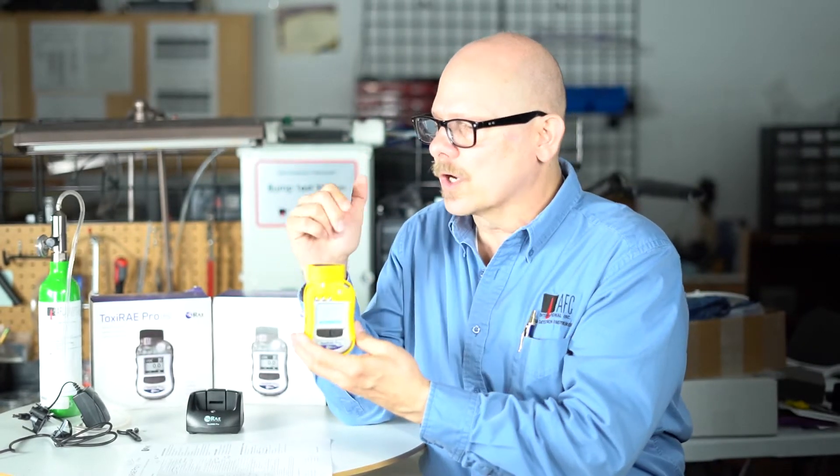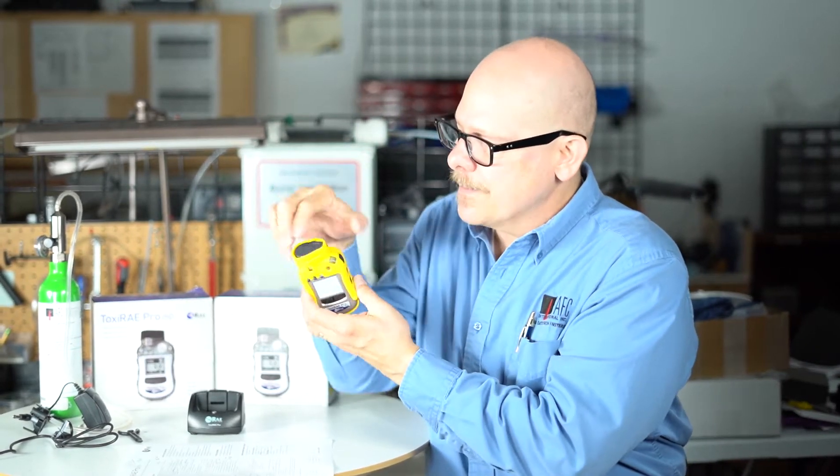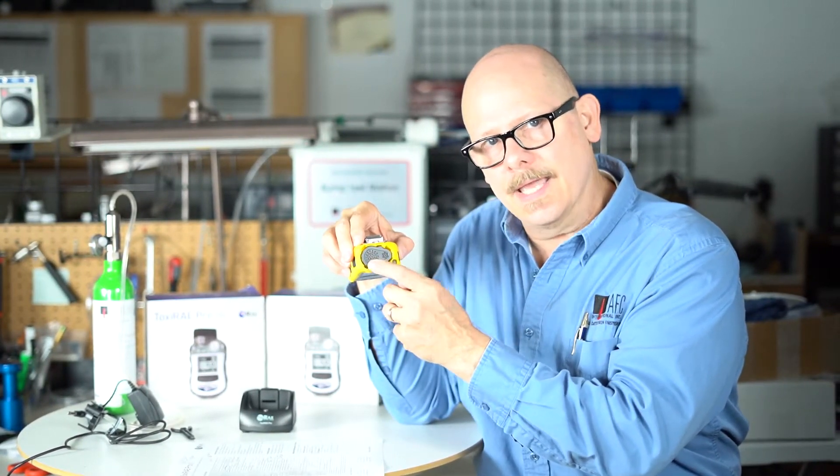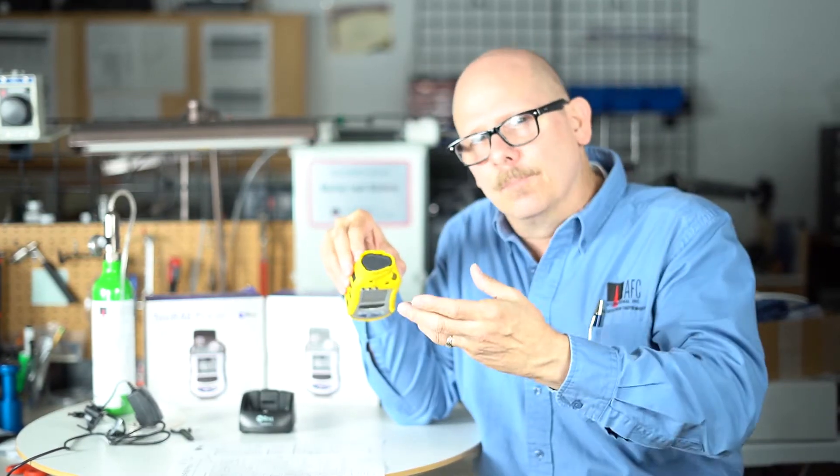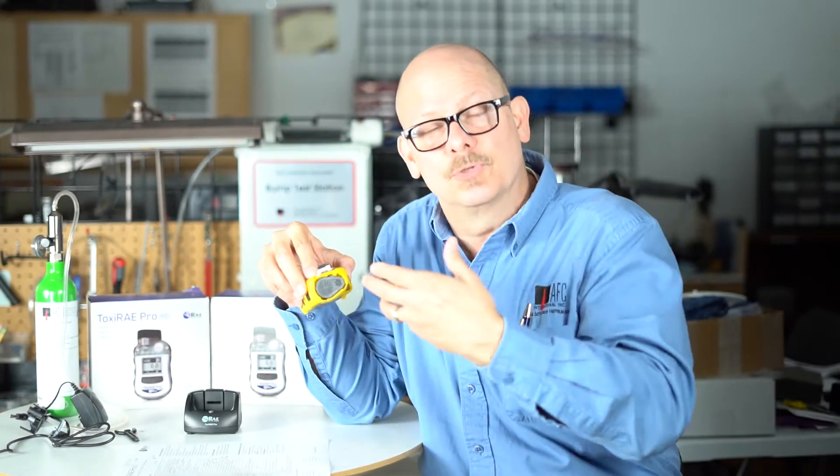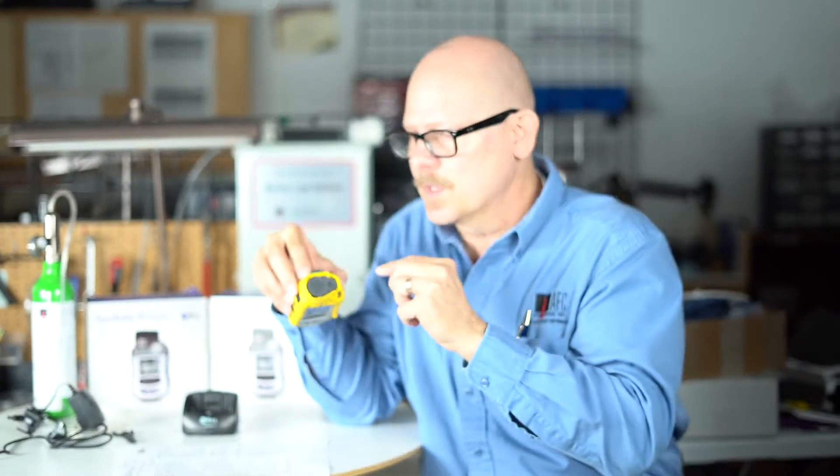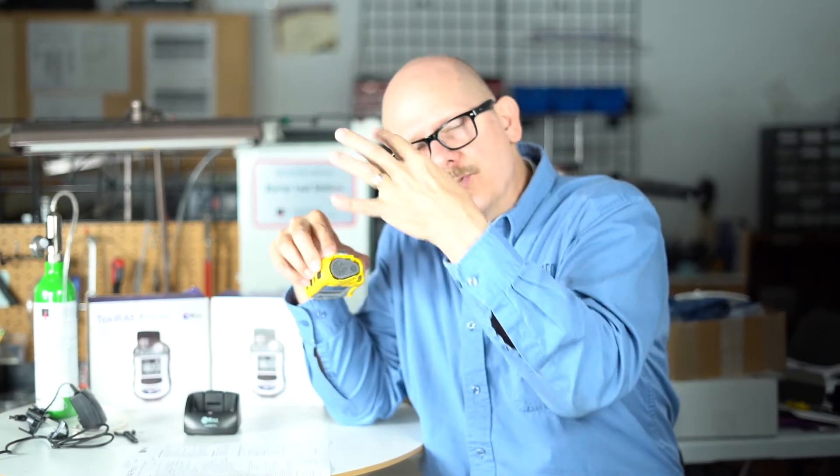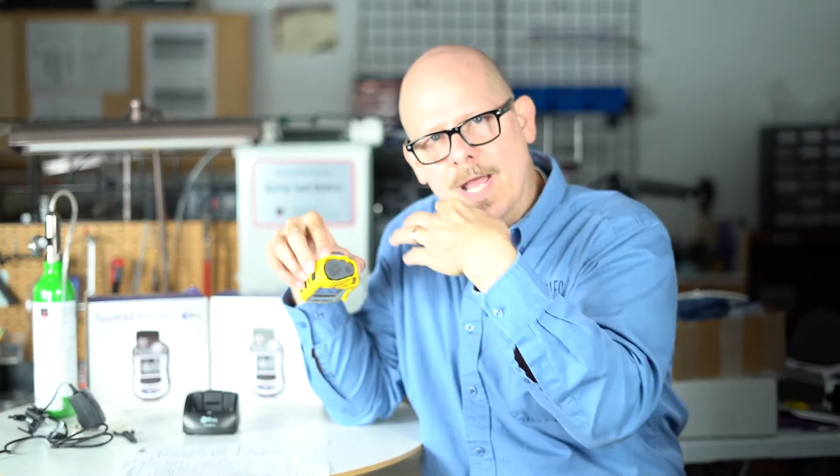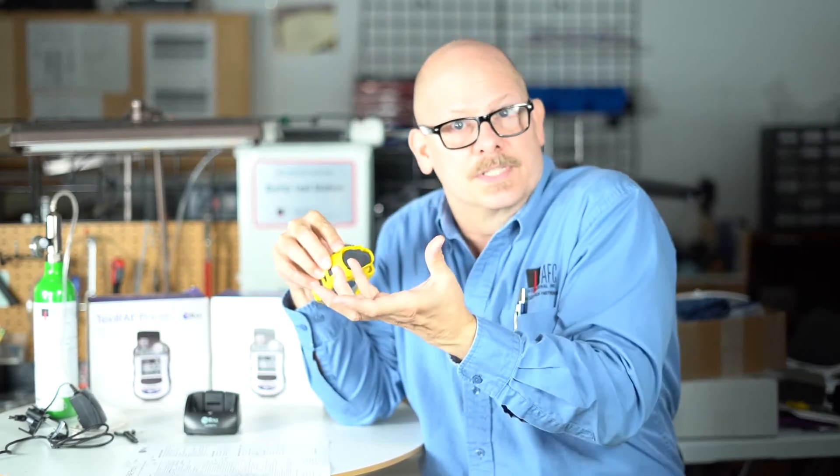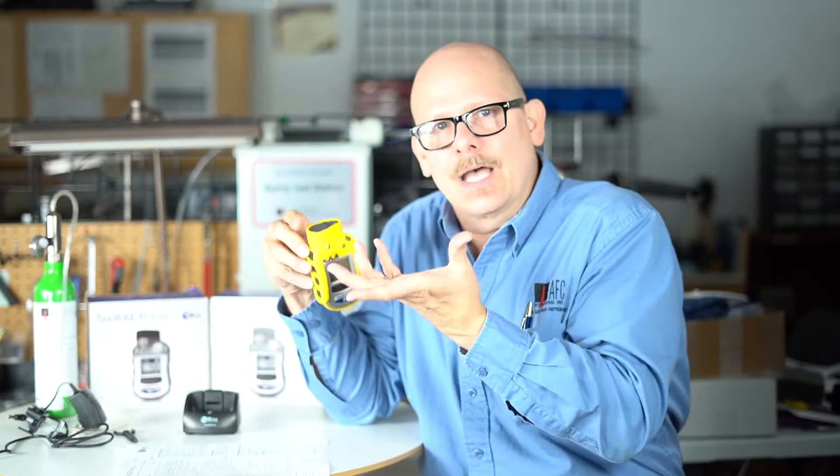How does this thing work? Inside, underneath this cap here, we have either a 10.6 or a 9.8 lamp. And instead of having a sample pump, like most of your RAE systems, MiniRAE 3000s and MiniRAE 2000s had a pump to pull the sample across that sensor. Instead of a pump, there's a little micro fan, and that little micro fan pulls the air and the sample around where the worker is and brings it into that ionization chamber or the detector and the sensor.